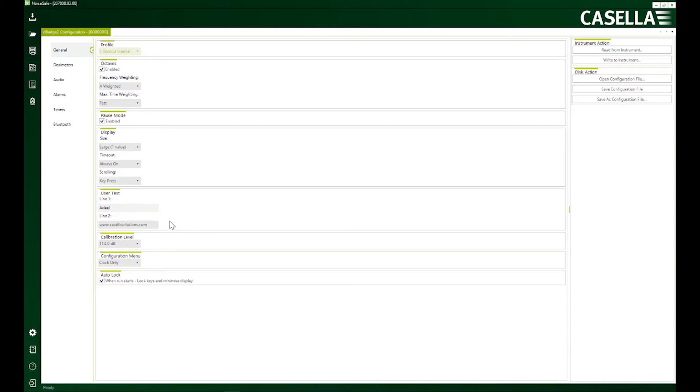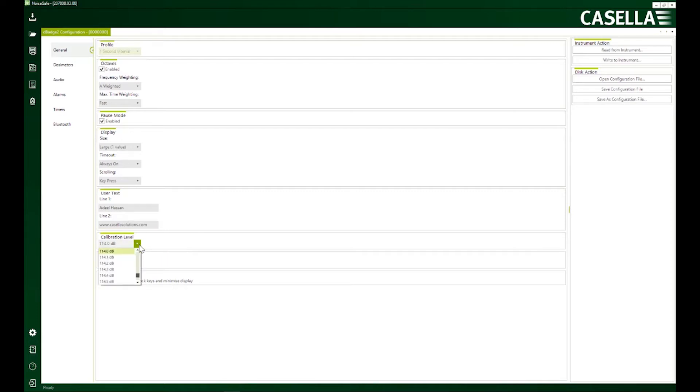I can personalize the device. So if I write my name here, my name comes up every time the device turns on. I can change the calibration level of my device here. 114 decibels is pretty much a norm in the industry.